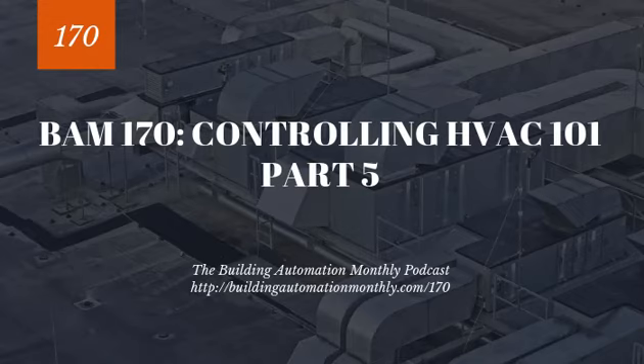Now, if you do have variable flow on a primary loop, and you'll see this in a couple different scenarios, you want to focus in on that as well, because you don't want the secondary and the primary loop fighting one another. All right, so primary secondary loop control.